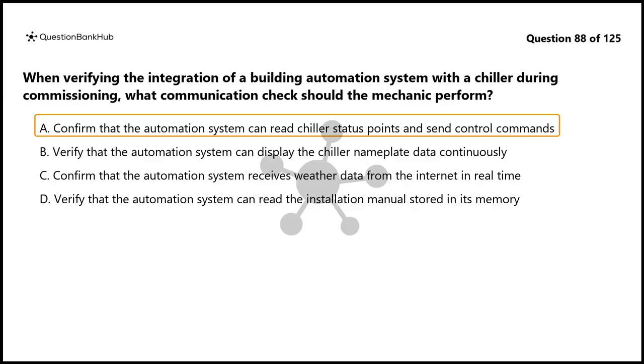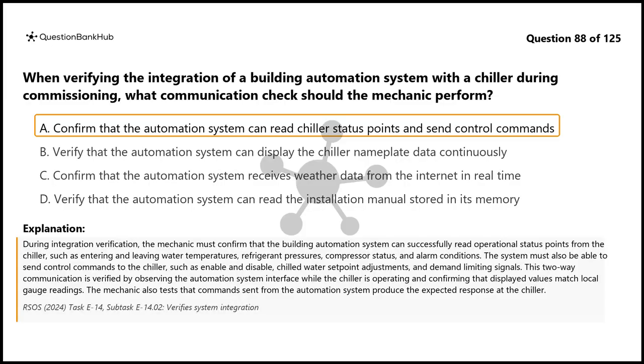The correct answer is A. During integration verification, the mechanic must confirm that the building automation system can successfully read operational status points from the chiller, such as entering and leaving water temperatures, refrigerant pressures, compressor status, and alarm conditions. The system must also be able to send control commands to the chiller, such as enable and disable, chilled water setpoint adjustments, and demand limiting signals.